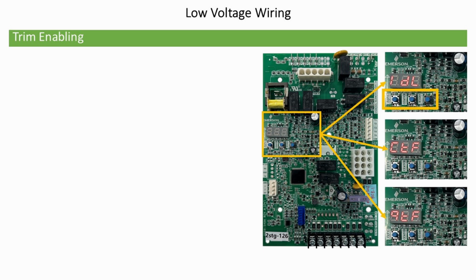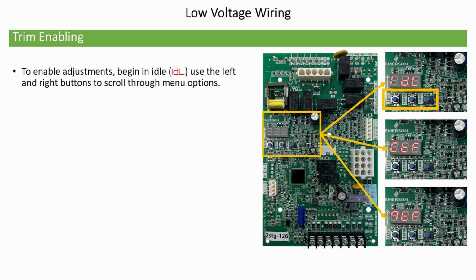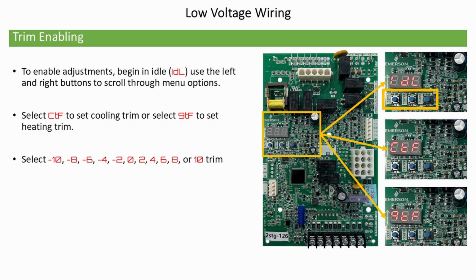Trim enabling. To enable adjustments, begin in idle. Use the left and right buttons to scroll through the menu options. Select CTF to set the cooling trim, or select GTF to set the heating trim. Select -10, -8, -6, -4, -2, 0, 2, 4, 6, 8, or 10 trim. Press the center button to confirm the selection.